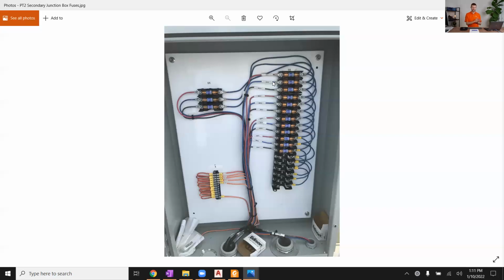But on the CTs, it was the other story. We didn't have fuses. Why didn't we use fuses on the CT secondary circuits? It's because we're going to intentionally short circuit our CT secondaries at times with our shorting test switches, shorting terminal blocks, et cetera. What we don't want on the CTs is an open circuit. So exactly, to not create open secondary on the CTs. You know, how does a fuse blow? When it blows open circuited. So if we used fuses on our CT secondaries, we would have dangerous open circuit voltage buildup, arcs, damaging CTs, et cetera. So don't use fuses on your CT circuits.